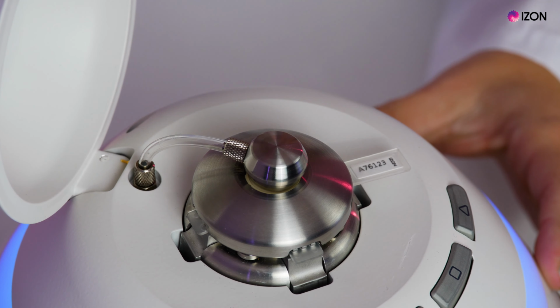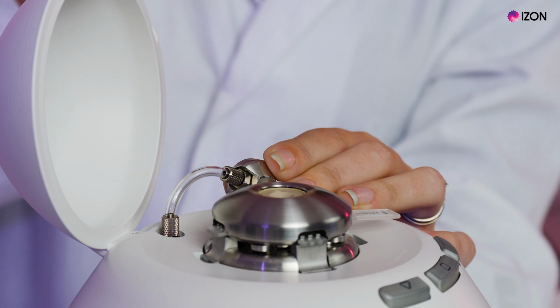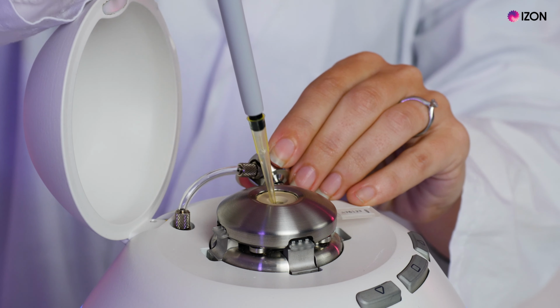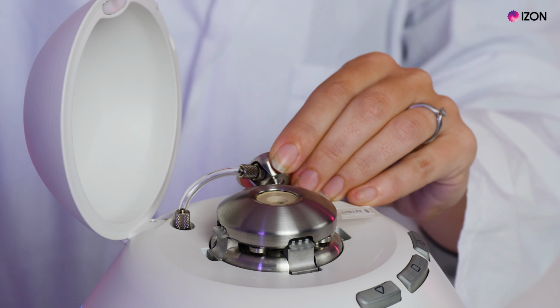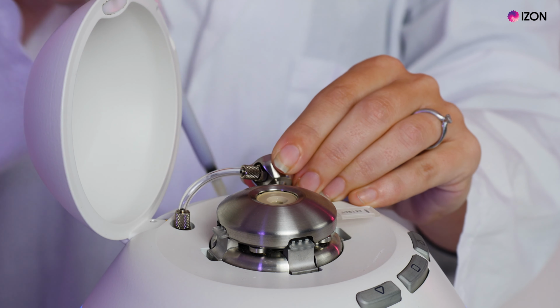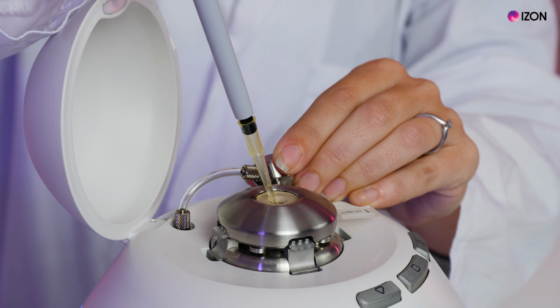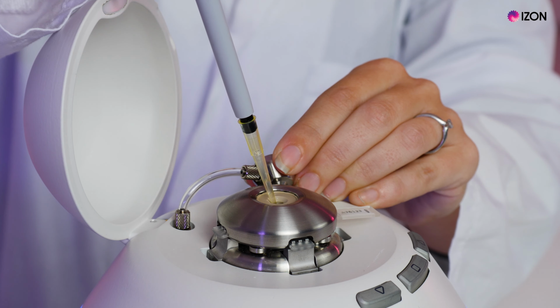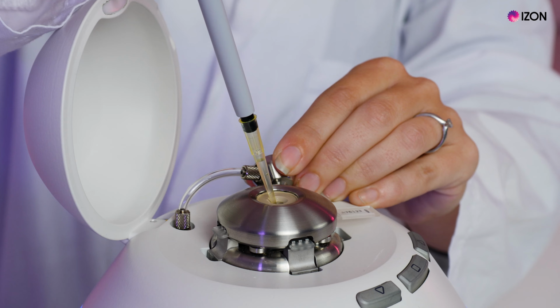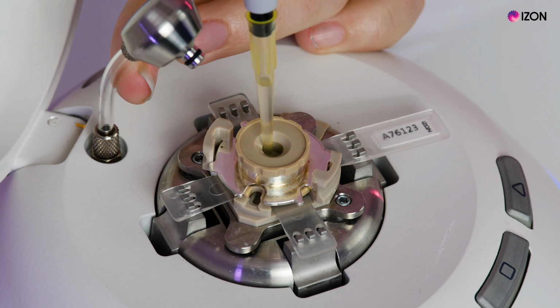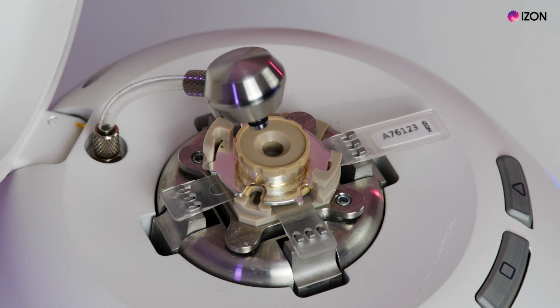Typically these measurements occur autonomously, but sometimes user intervention is required if the nanopore gets blocked by large particles or bubbles. This intervention is usually a sharp tap on the pressure nozzle with the back of your pen, or plunging the system with the plunger. Once calibrated, the user is then guided through washing the system to prevent cross-contamination of samples and calibration particles. This is achieved by washing the fluid cell with fresh measurement electrolyte with a pipette. Once the wash program checks the pore and the fluid cell is clean, the user is prompted to load their sample. The sample is then measured 3 times under the same parameters as the calibration.